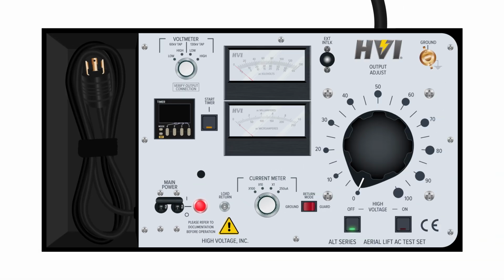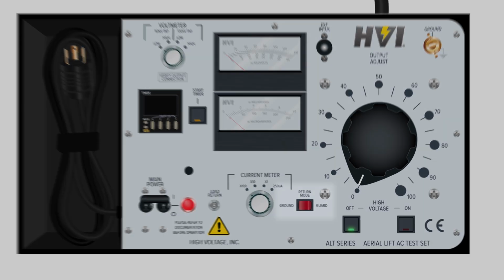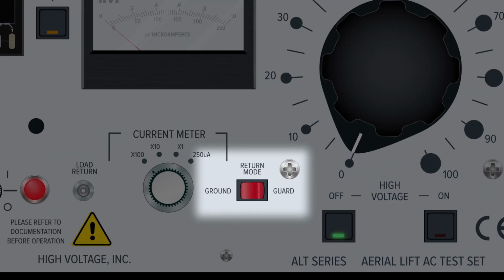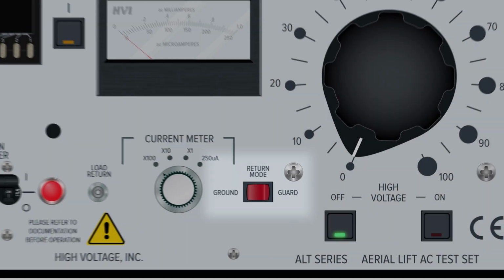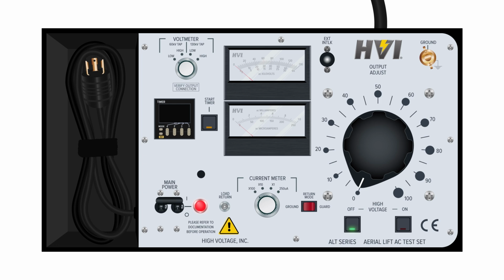ALT series Hipots have two return modes, which are controlled by the return mode switch, located at the bottom of the panel, directly to the right of the current meter switch. When the device is set to ground position, the current running through the ground lead and return lead will display in the current meter.